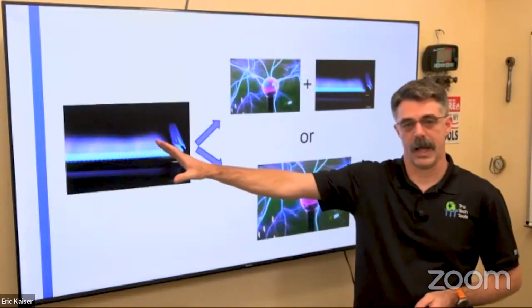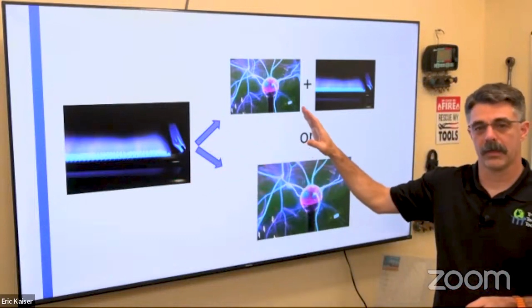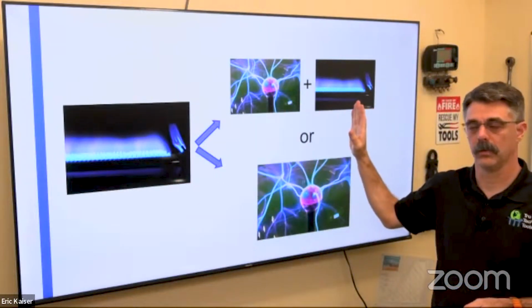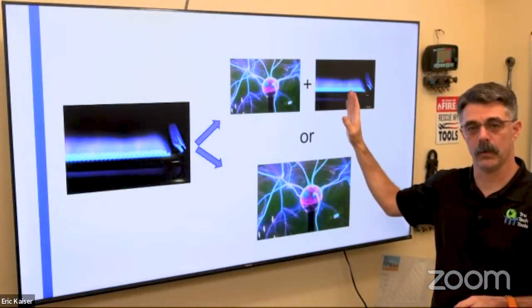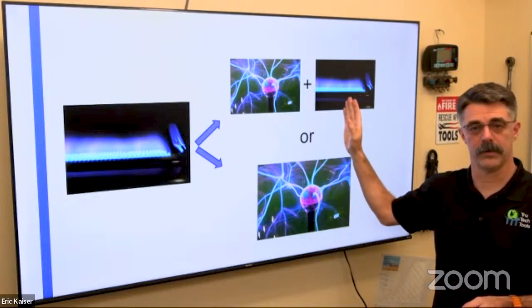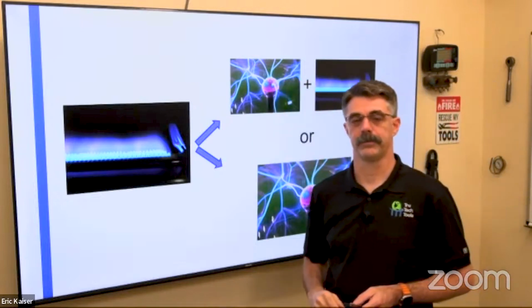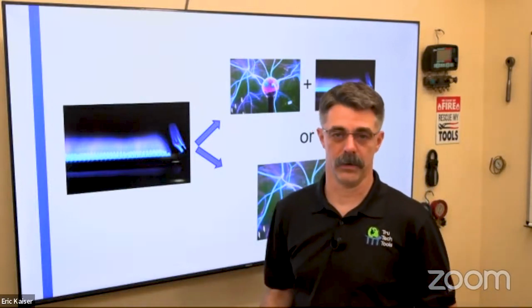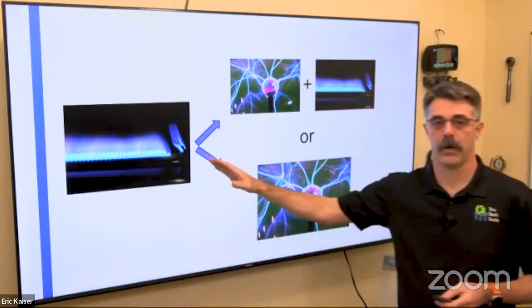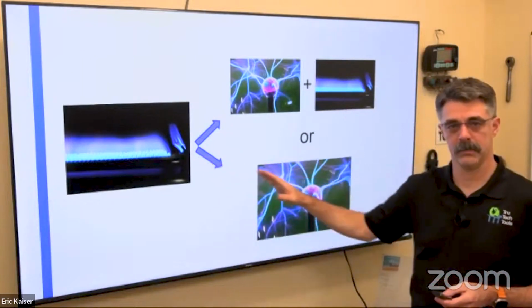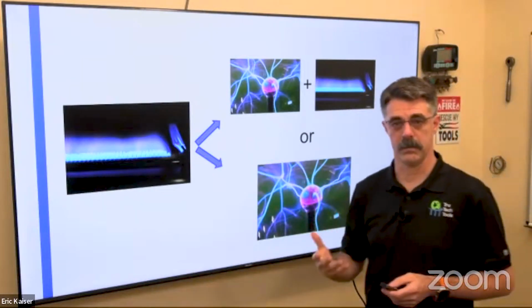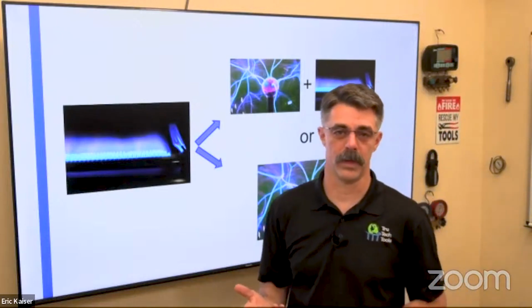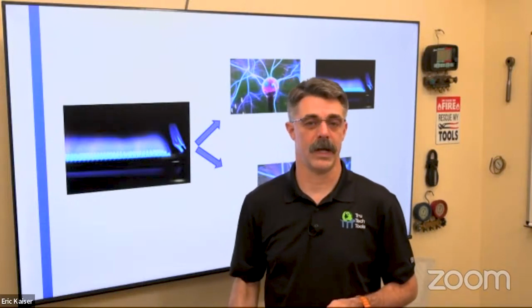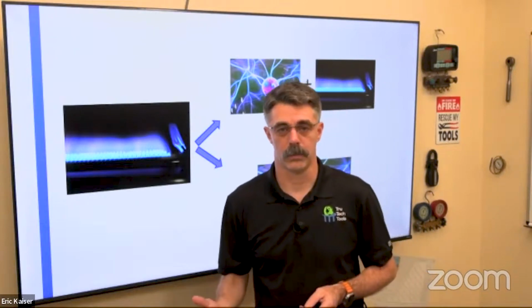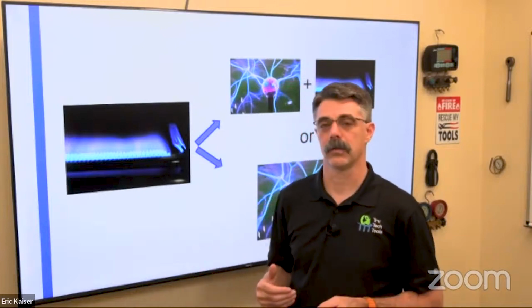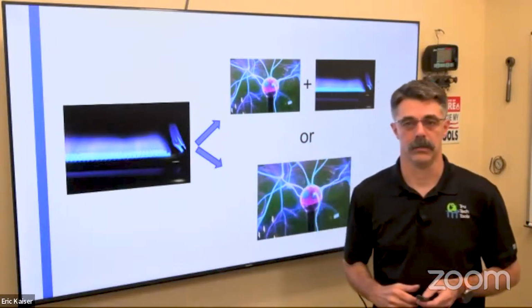Remember, we're going from a gas or an oil-fired appliance. One pathway is what's called dual fuel, where we keep that fuel-fired appliance, or maybe put a different fuel-fired appliance in, and we stack a heat pump with that. We use them, one or the other, to provide heat. The other pathway, coming from a straight fuel-fired appliance, is we go 100% electric with a heat pump. And if it is a cold enough environment where the heat pump cannot provide heat to the house 100% of the time, we may supplement that with a little bit of electric resistance heat. We're going to talk about some of that tonight too.